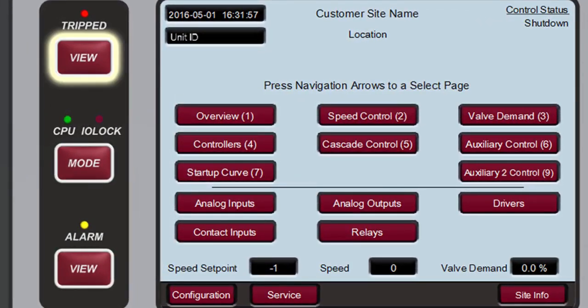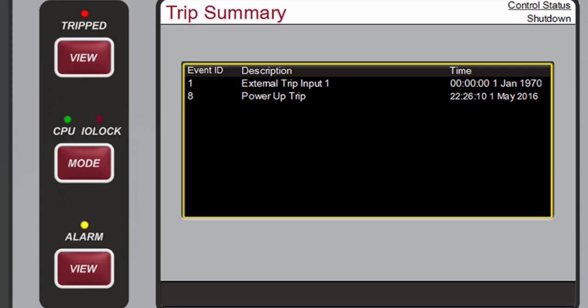Let's cover each of these buttons. Pressing Tripped View opens the Trip Summary screen. When a trip is detected, it gets latched in the event logic. The trip relay is de-energized, all steam valve demand outputs go to zero, and the tripped LED illuminates red. The cause of the event will be indicated with an event ID, description, and time and date stamp. The list will always place the first trip condition to occur at the top of the list. The most recent trip condition to occur will always be placed at the bottom of the list.